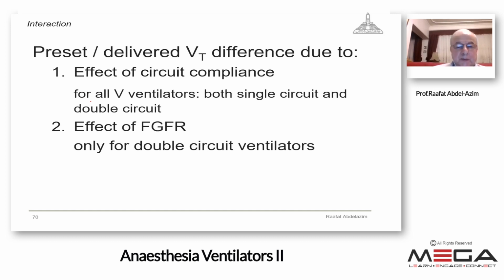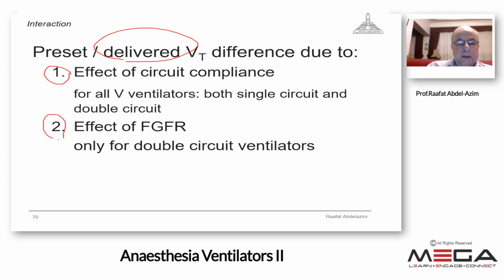The other factor will add, this is the effect of fresh gas flow, and this fresh gas flow will add to the preset tidal volume. So it is not always the situation of having the delivered tidal volume the same as the preset. Something will subtract and something will add. Circuit compliance means the expansion of the circuit due to the positive pressure. This expansion will lead to loss of some part of the tidal volume delivered to the patient. And the fresh gas flow, of course, it is addition, as I explained before.